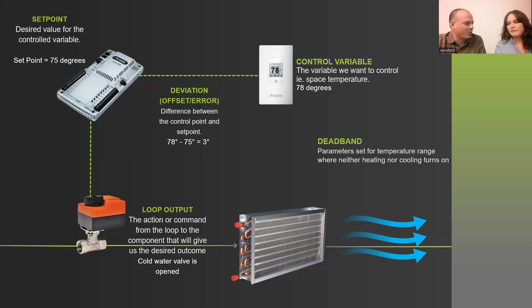And that's where the deadband comes in. One thing you can consider is that in the range of the deadband, the controller output isn't really responding; the loop is not responding in that range. And that keeps everything more comfortable because you're not waiting for things to get ultra warm or ultra cool in order to turn it on, but it also saves on runtime because you're not immediately turning things on and off. So there comes that energy efficiency that controls is trying to manage. We're always trying to balance between efficiency and optimal comfort, to your point.